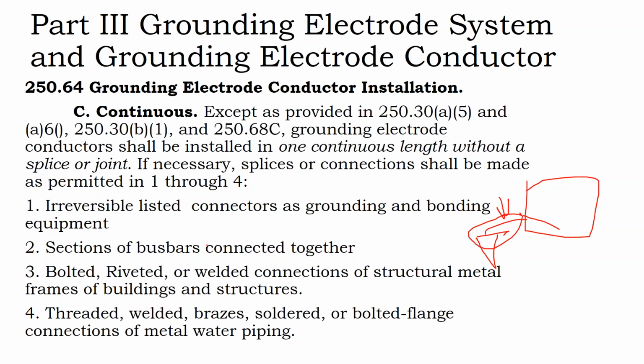Well, it depends if it's the grounding electrode conductor or not. The grounding electrode conductor can just run up and lug on to the end of the racking. And if your modules are bonded to your racking, then no, you can just make a bonding jumper from that point to make sure all of your equipment's connected together. But that last leg of the journey needs to be a continuous run.